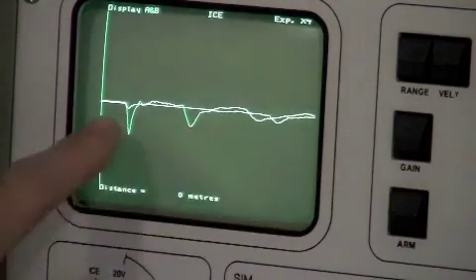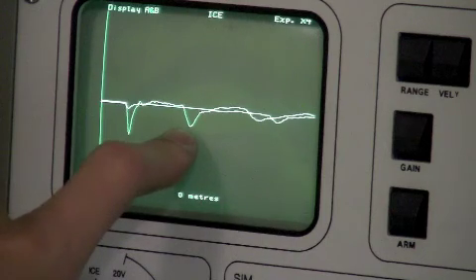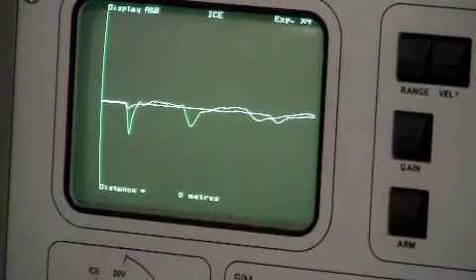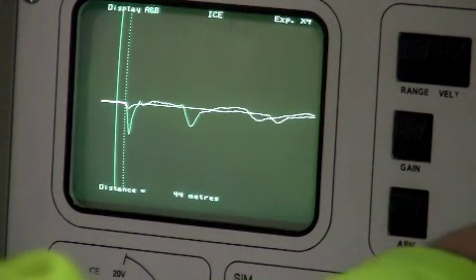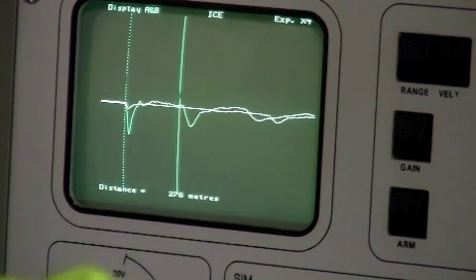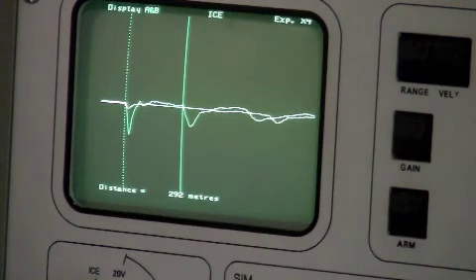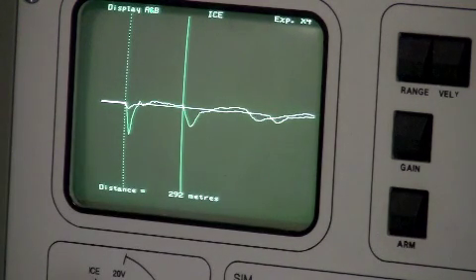If we overlay the two traces together we can clearly see the fault location. I have two cursors. If I adjust the first cursor to where the test cables are connected and bring the second cursor to the start of the dip, I'm now shown the pre-location of fault position at 292 metres.